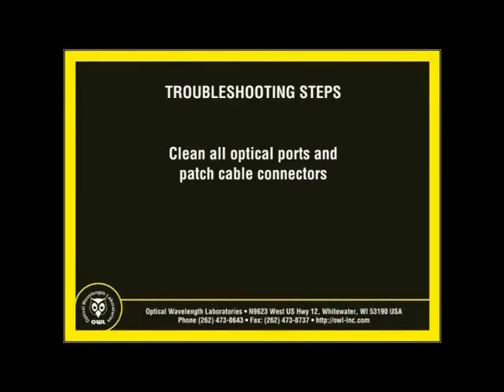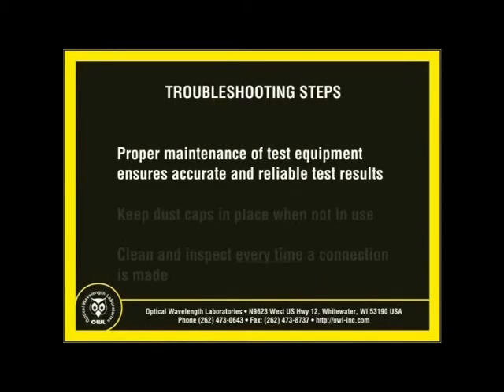If the power level falls below the acceptable power level range, debris such as dust, dirt, or finger oil may have collected on the connector end face or in the equipment's optical ports. Thoroughly clean and inspect all connector end faces and equipment optical ports according to industry standard cleaning procedures. Several cleaning cycles may be required. Keeping connectors and optical ports clean at all times helps to keep test equipment in good working order and proper calibration, ensuring accurate and reliable test results.